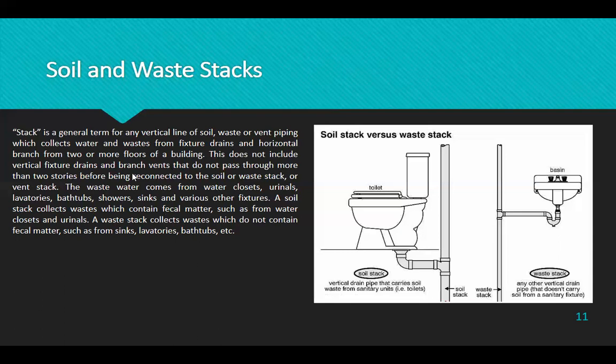This does not include vertical fixture drains and branch vents that do not pass through more than 2 stories before being reconnected to the soil or waste stack or vent stack. So bale nagbabypass dyan ng vent, so hindi kasama. The wastewater comes from water closets, urinals, lavatories, bathtubs, showers, sinks, and various other fixtures. A soil stack collects waste which contains fecal matter, such as from water closets and urinals.